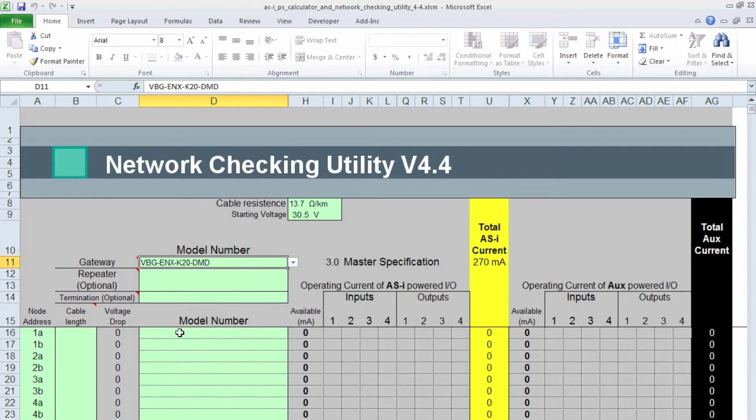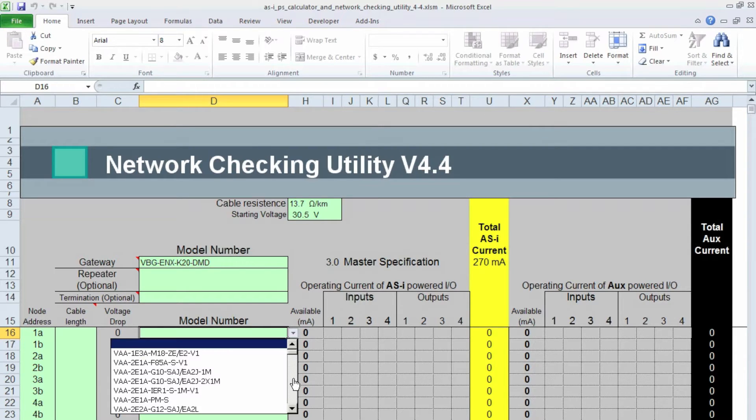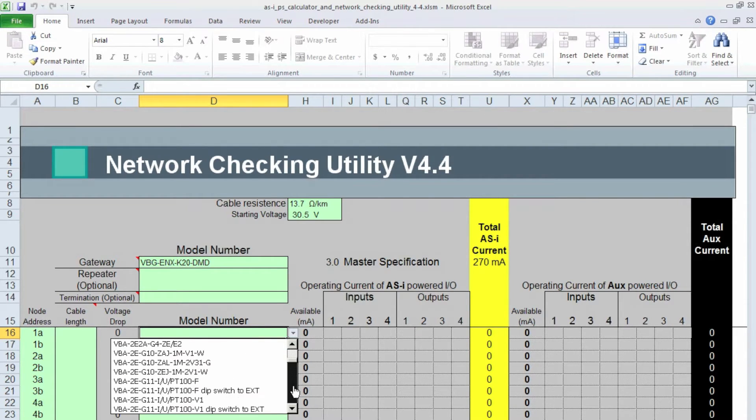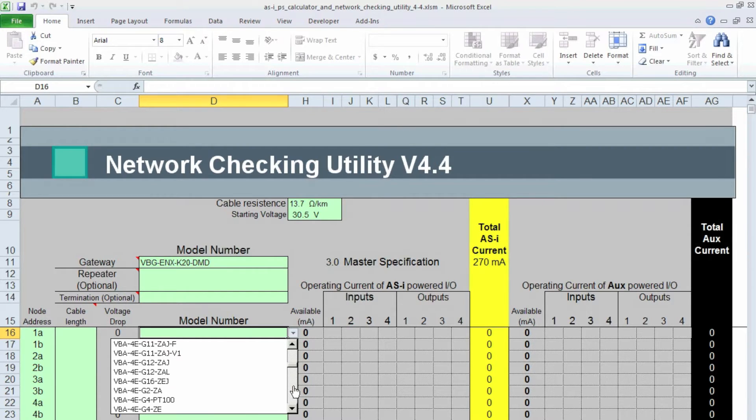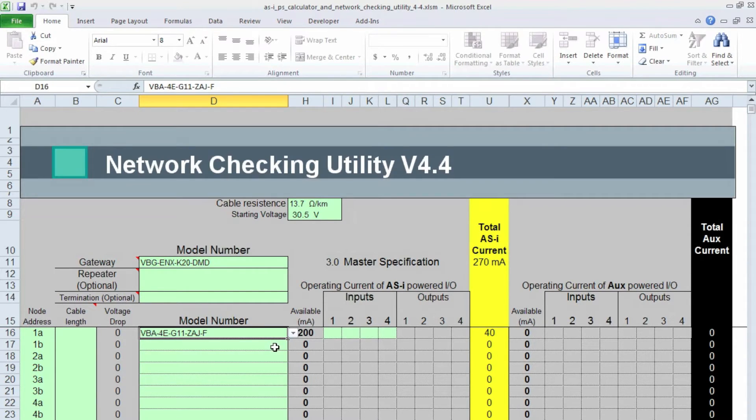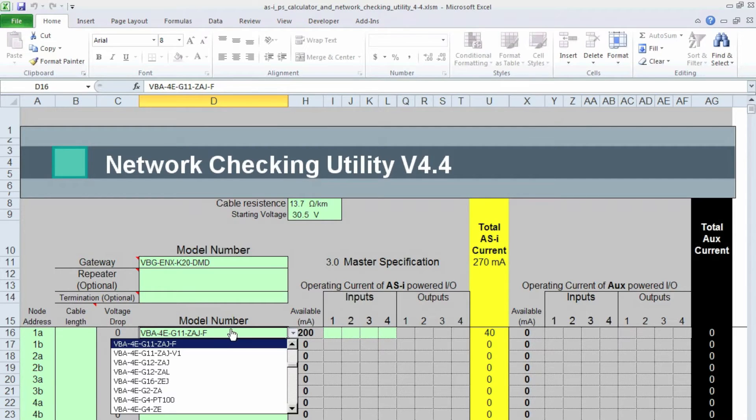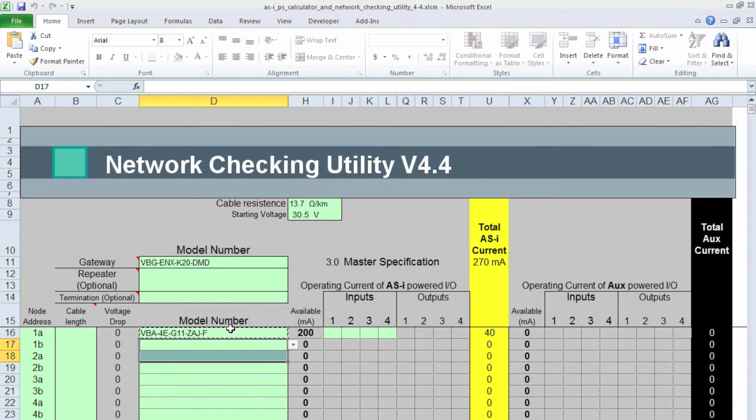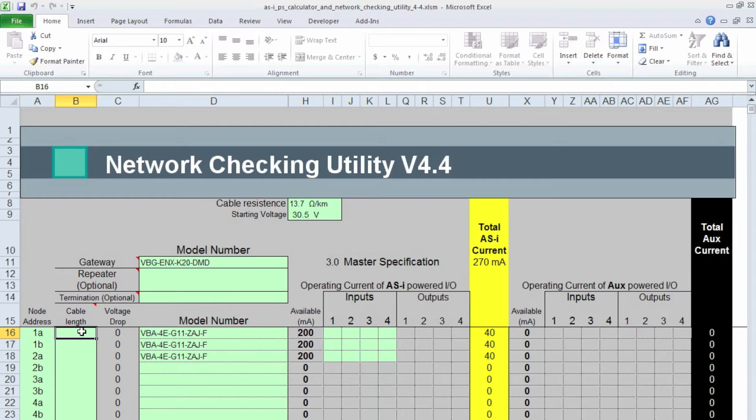And then I need to choose the I/O module. So I know it's a 4-input G11. So VBA-4E-G11. All right, there you go. So with selection of that module, it tells me how much current is available, and it wants me to fill in the operating current of each sensor. And because I've got three AS Interface Modules on the network, I'm going to just copy this one and paste it two more times.